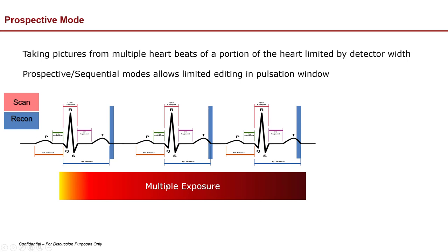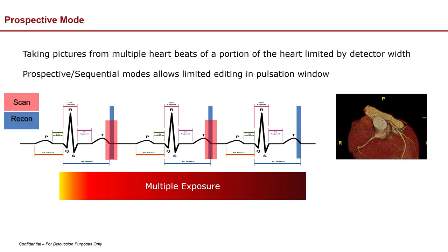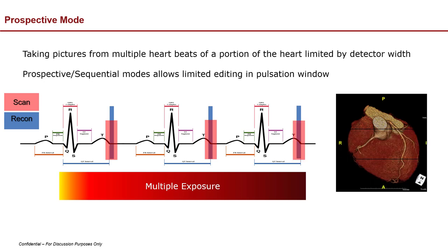The problem with most CT scanners is you can't cover the entire heart in one rotation — you take a set of pictures corresponding to the detector coverage. A 64 or 128-slice scanner will have about a 4-centimeter detector, so you get 4 centimeters at a time. Each time the table moves and takes another picture, you get another 4 centimeters. If your heart isn't exactly the same size and shape, you'll get an artifact and it won't line up.